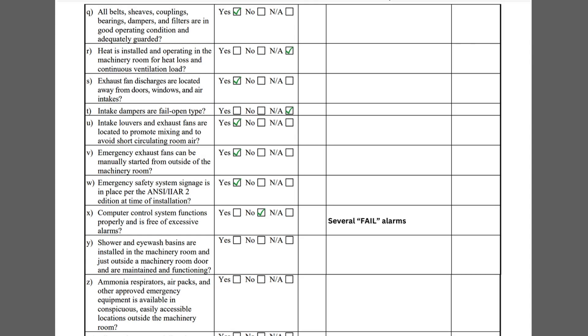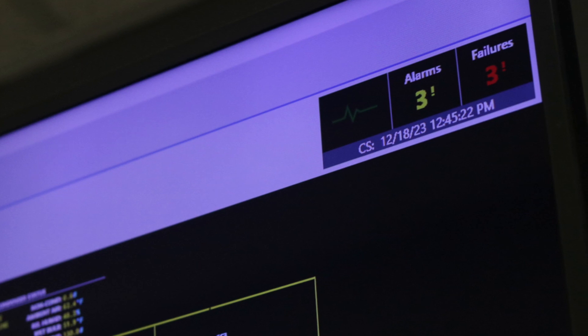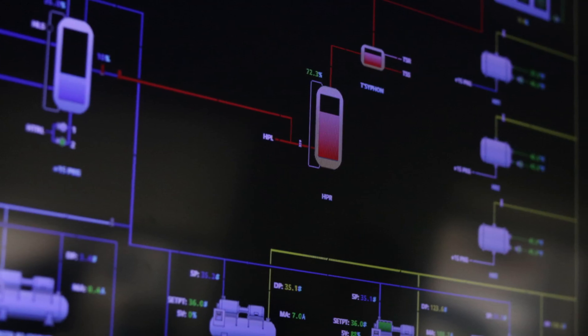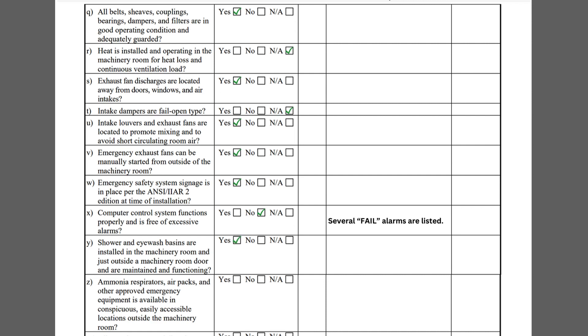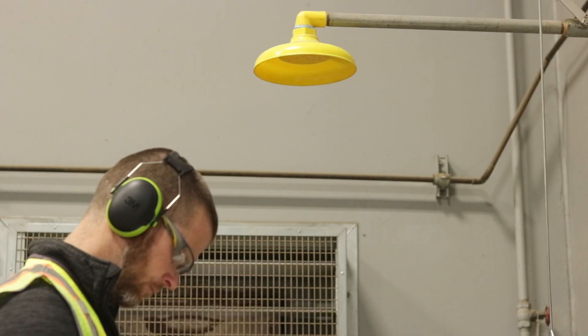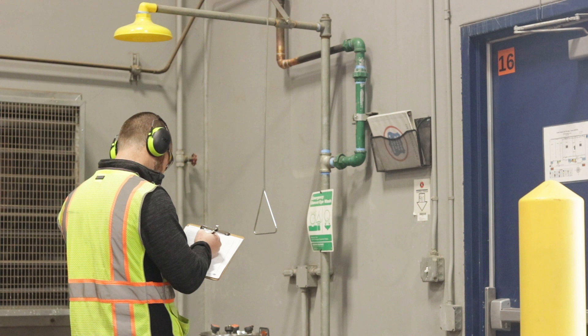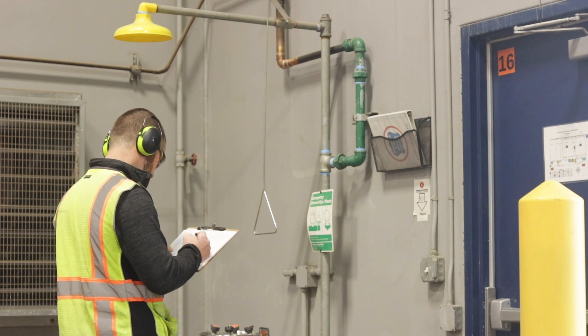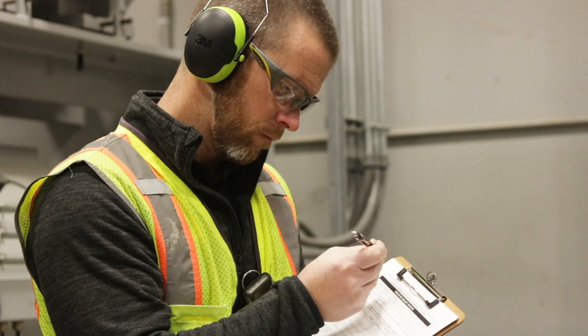Item X asks if the computer control system functions properly and is free of excessive alarms. A computer control system HMI is located in the maintenance office and is visible to maintenance personnel on a big screen TV. Item Y asks if the shower and eyewash basins are installed both inside and outside the machinery room, and the inspector must verify that they are functional. Checklist Item Z asks if ammonia respirators, air packs, and other approved emergency equipment is available in conspicuous, easily accessible locations outside the machinery room. This is a non-responding facility that relies on local first responders for emergency response situations, so this question should be answered NA.